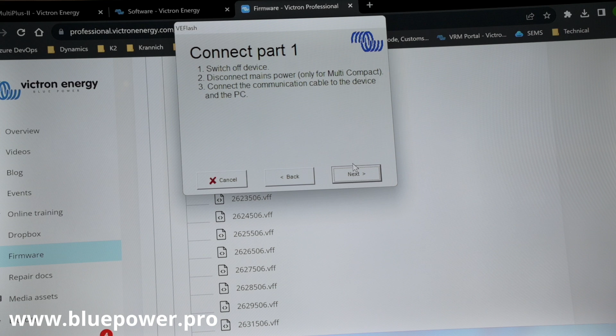Now it's asking us to connect part 1. It's telling us to switch off the device, disconnect the mains if we've got a compact, and connect the communication cable. So we can just switch it off again back to position 0. And we've got our comms connected, and we can click next.